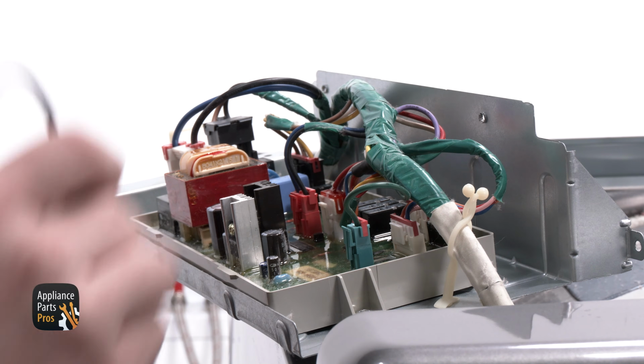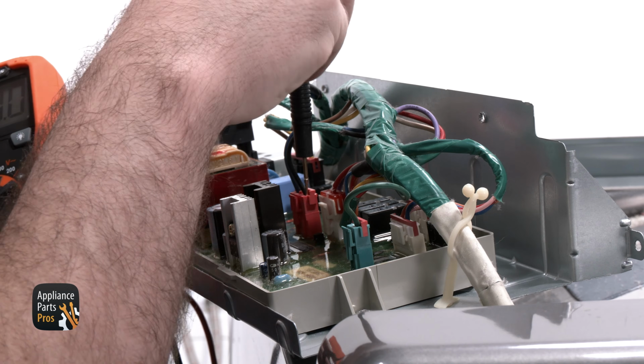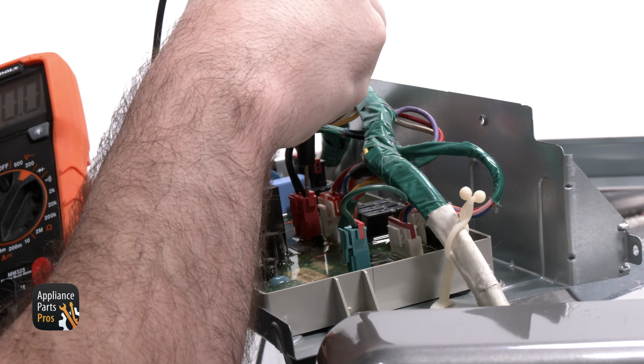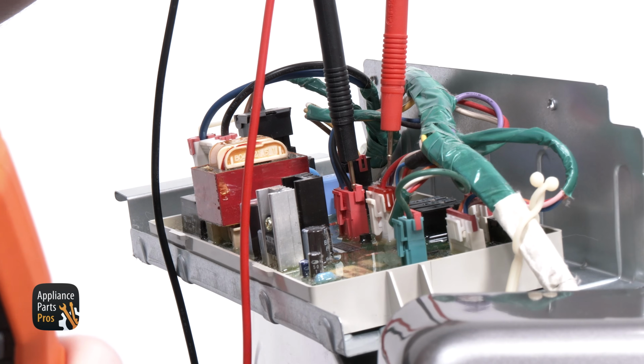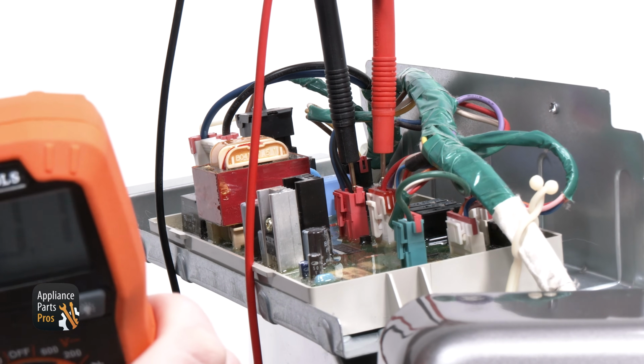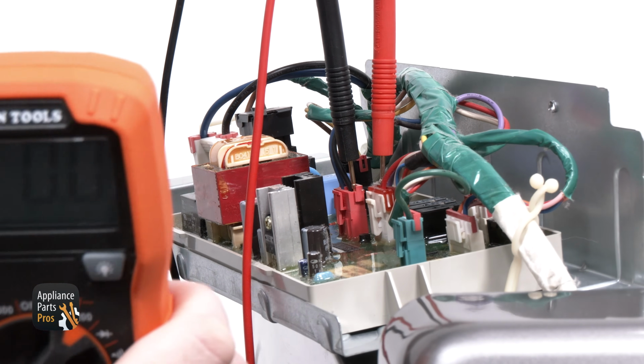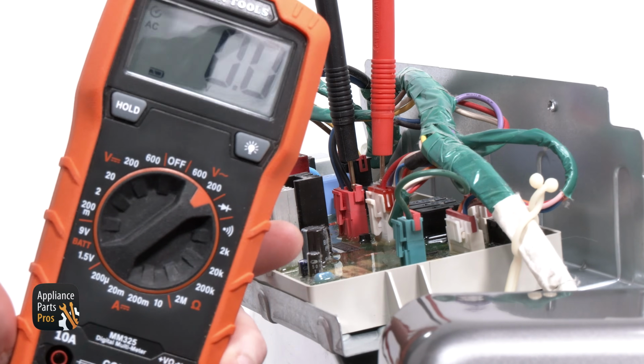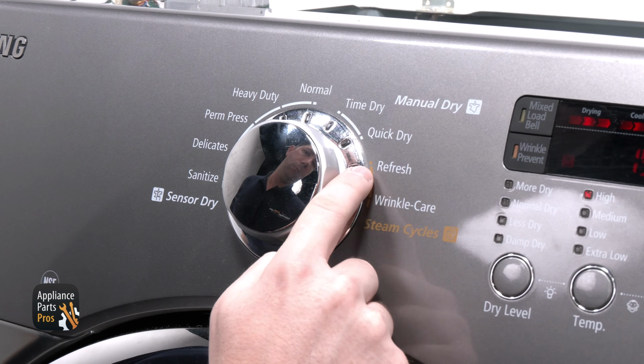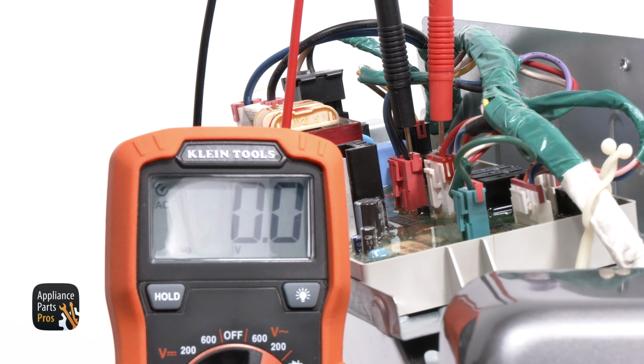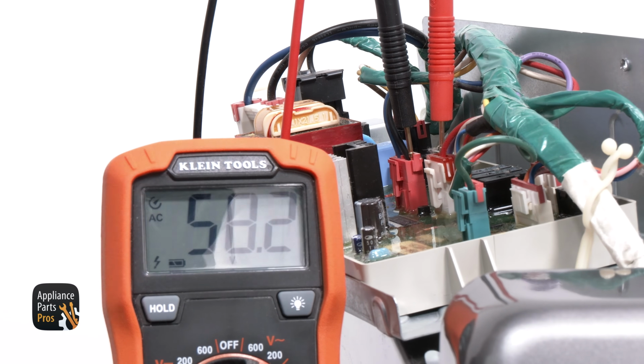We're setting our meter to volts AC, which looks like a V with a squiggly line. Then we're placing our black meter probe at the black wire on connection CN7, and it's going to stay here. We're using the red probe on the white wire and the red wire of connection CN5, which is just to the right of CN7. We're starting with the red probe being set to the white wire, and then we're going to start a steam cycle. There should be 120 volts AC within 2 minutes.